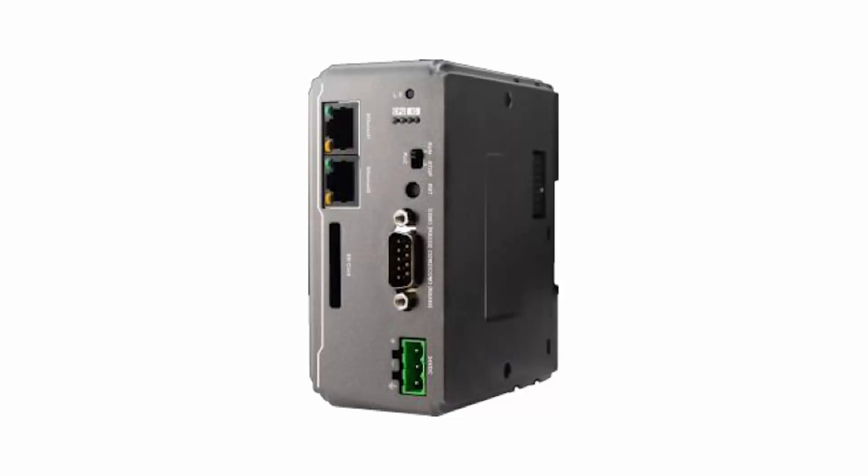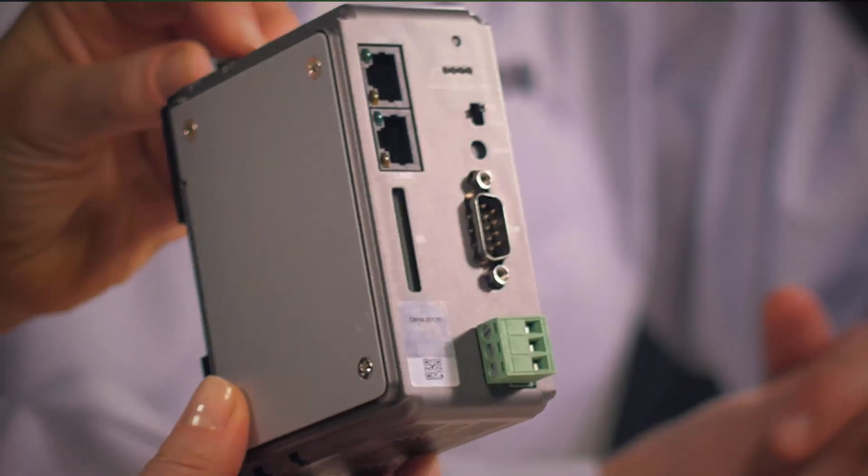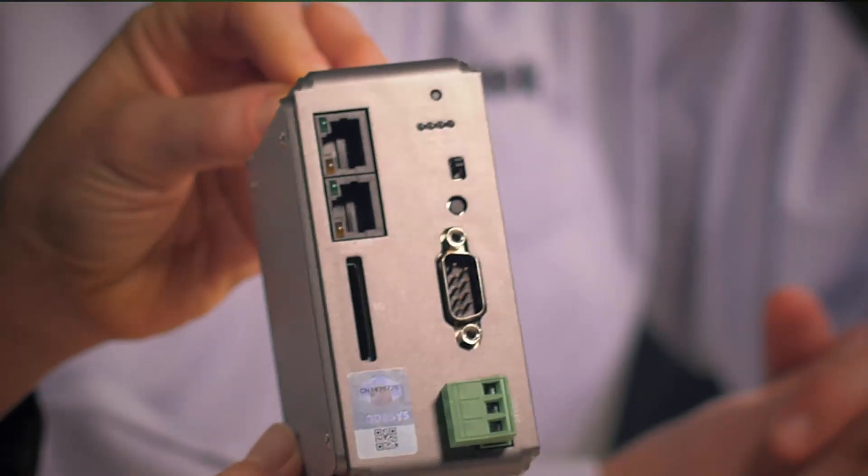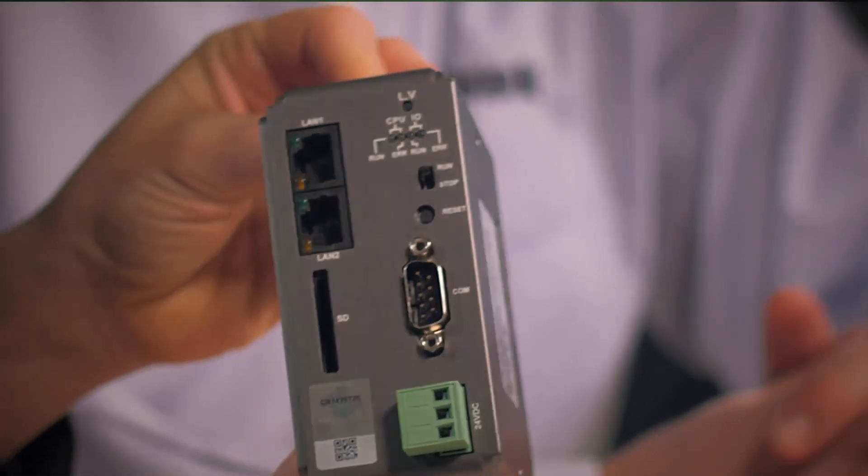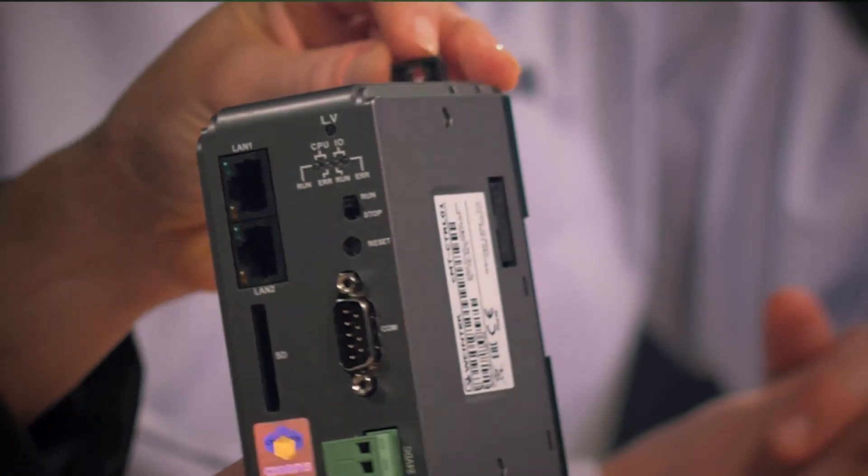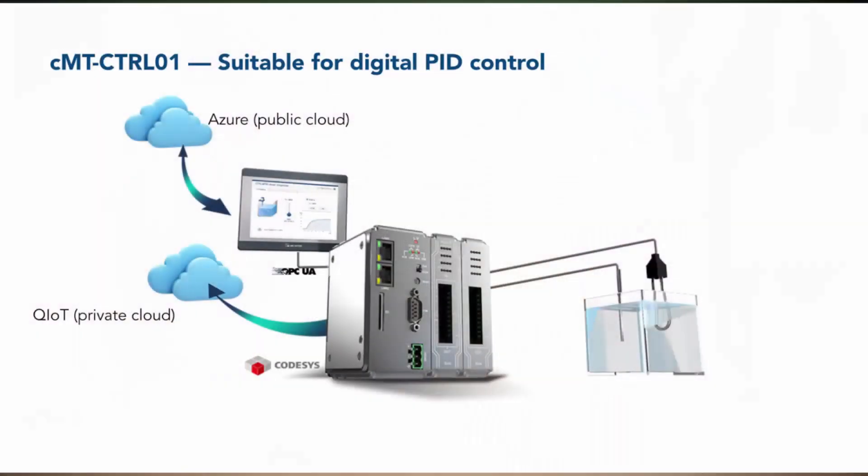The dual Ethernet ports on the CMT-CTRL-01 can be freely assigned so there's one Ethernet port for CodeSys and the other one for IIoT gateway. Or both Ethernet ports can be used for the IIoT gateway, with one port connected to the host computer or Internet, and the other connected to an on-site Ethernet-based PLC.